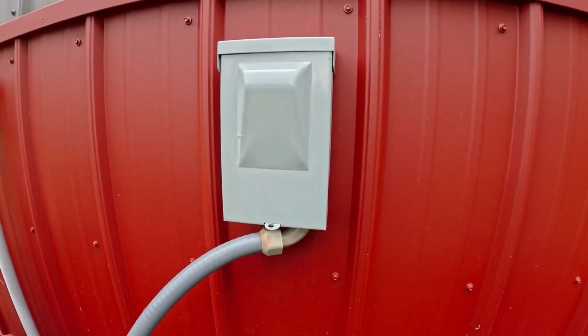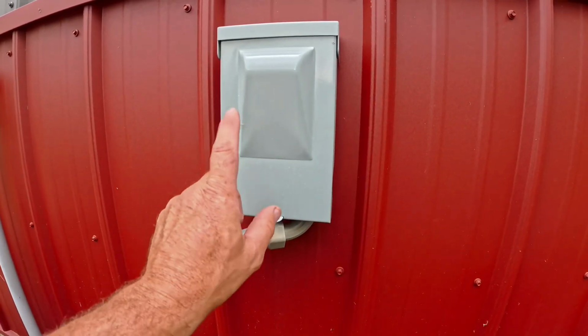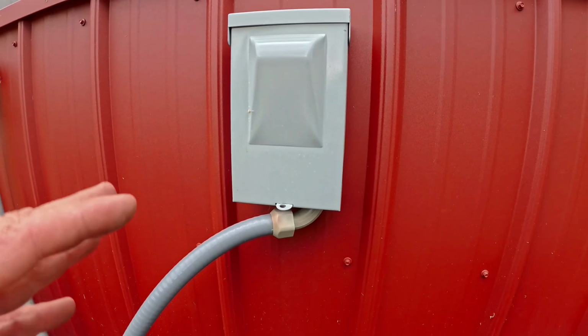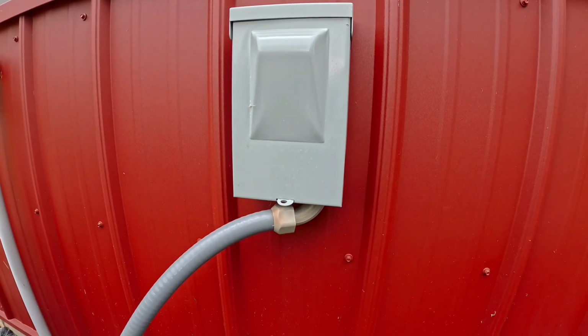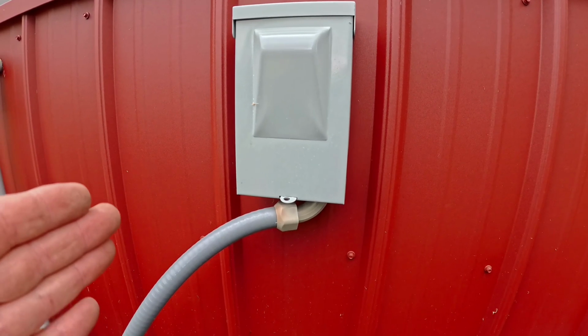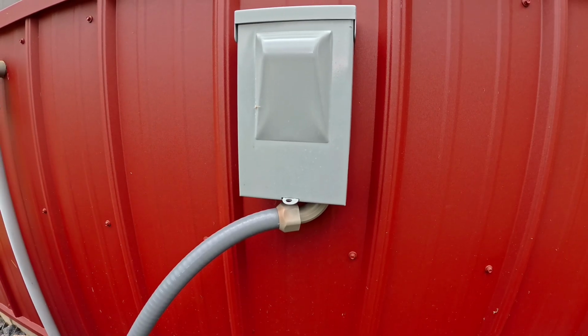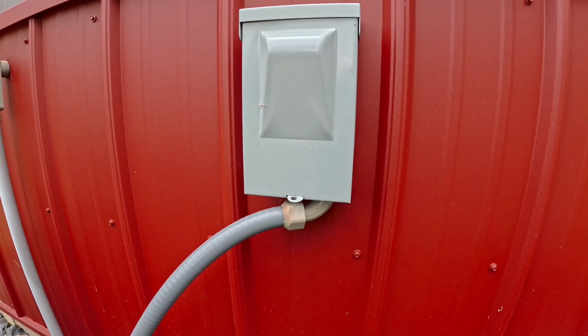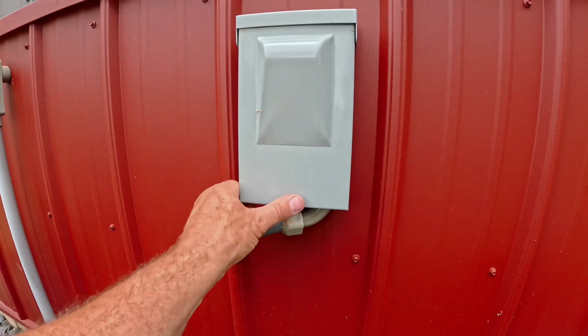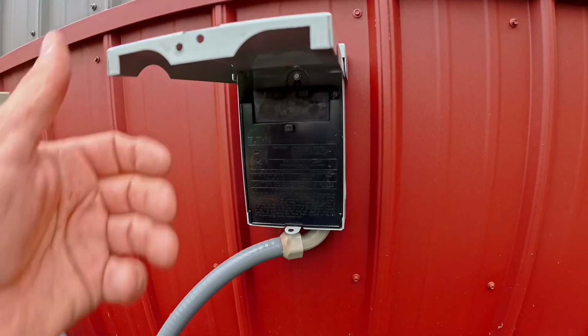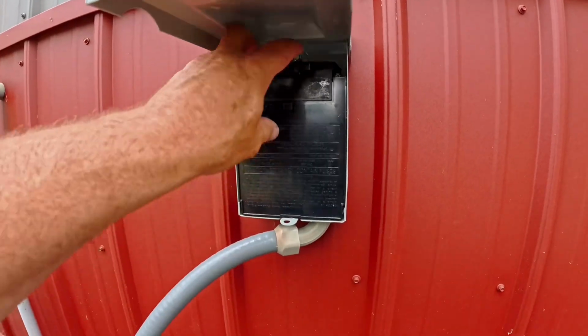So first things first, let's just check our voltage, make sure we got power coming out here. Easiest thing first, check the breaker inside, make sure the outdoor 220 breaker is on or not tripped anyways. If that's good, we're going to come out here to our service disconnect, pretty much open that up nice and easy. I know it's hard to see. We're going to check our disconnect.